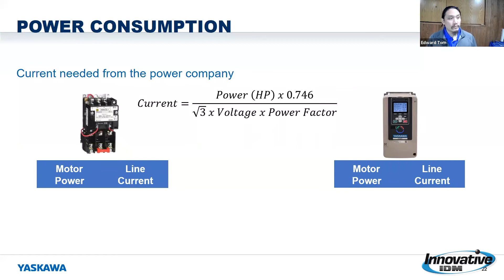So using this particular motor, if I was drawing its full power at 100 horse, I'm going to be seeing about 113 amps on there. So not too bad, reasonable. But on a VFD, I'm at 107. Same motor, but we've put a VFD in front of it. Slightly less losses on there. Okay, well, maybe it's just a little bit of calculation error, we might say.